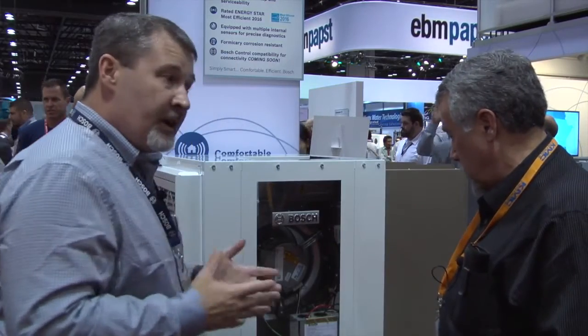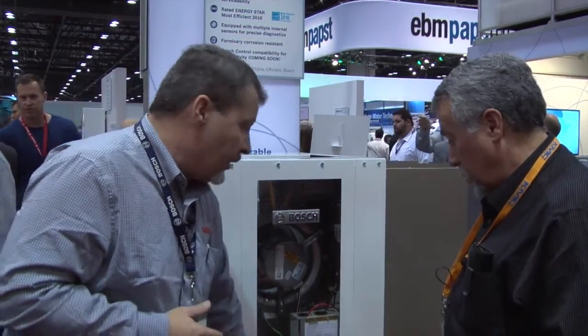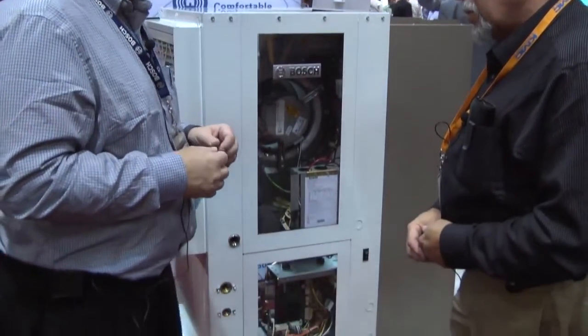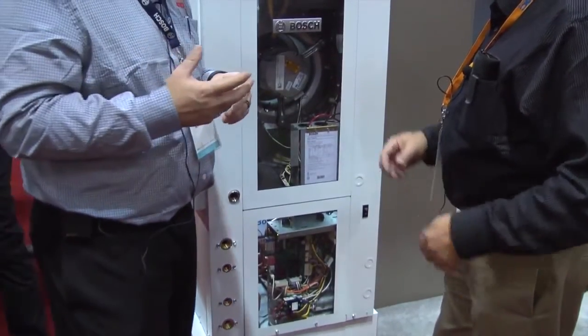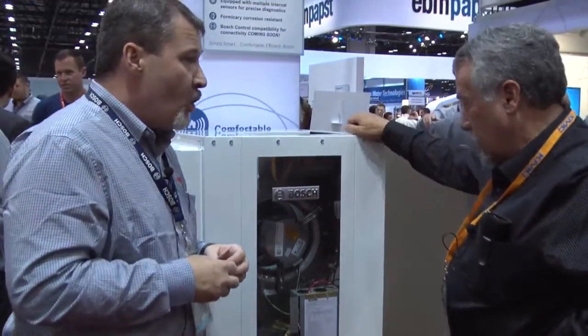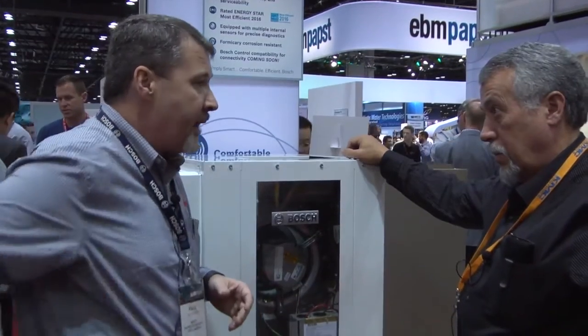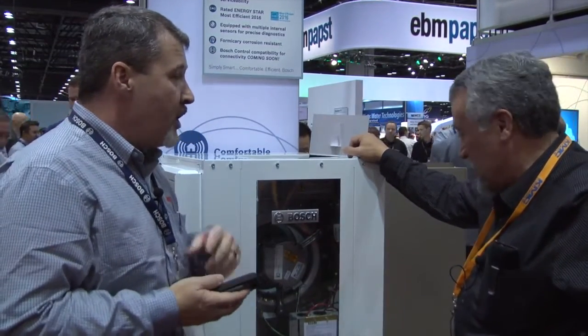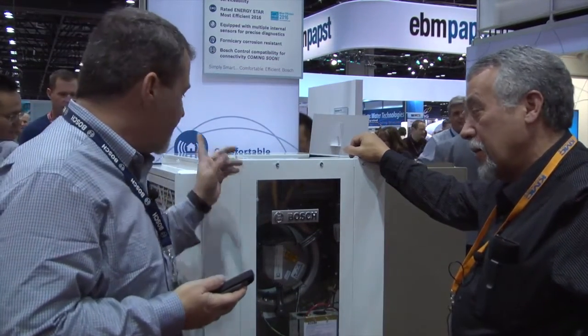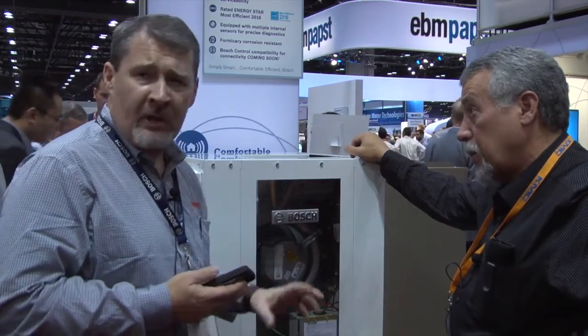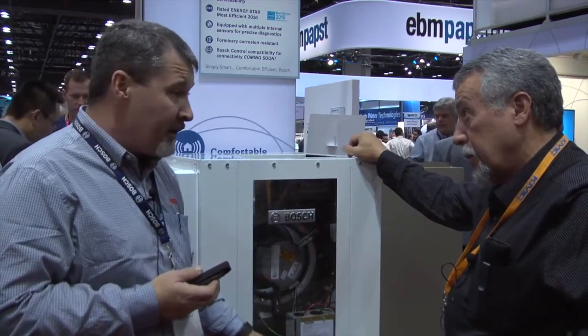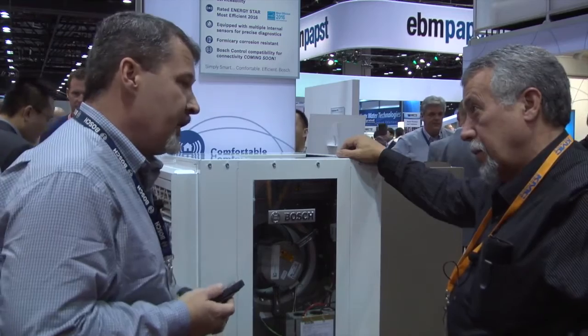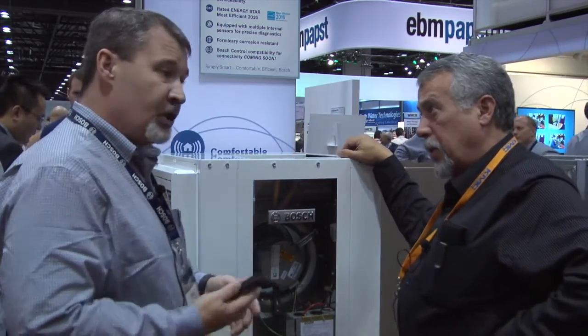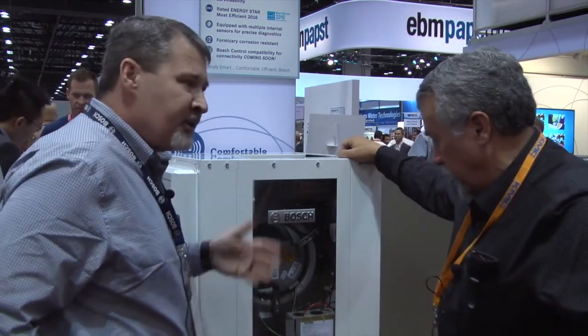The next thing we have is we built that to a 2-wire communication. What that gives us the ability to do is operate our new RRC control, which is fully cell phone capable. As long as it's hooked up to the internet, it's just a 2-wire connection, where most thermostats require up to 8 wires, ours will actually require 2. Is that shielded twisted pair? Shielded twisted pair, yep, very similar.